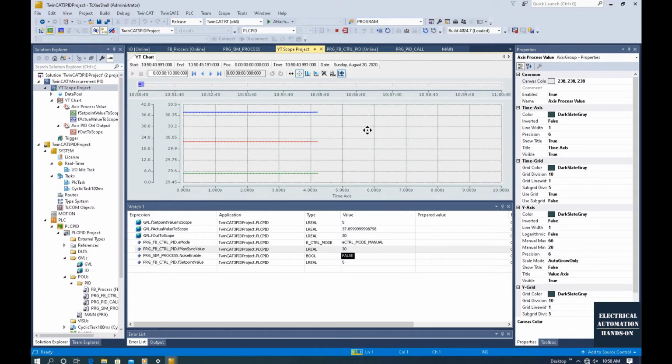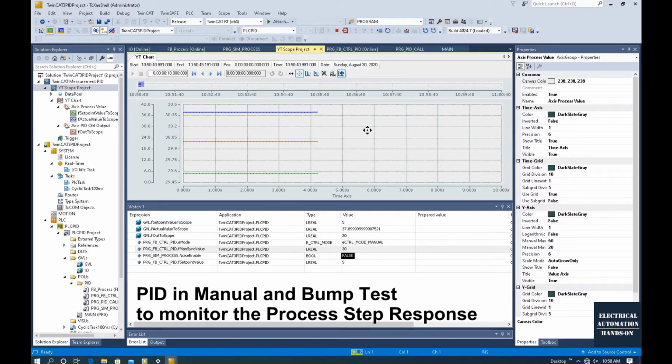So how can we select one value as the initial value of the gain? From my personal experience, we can give the system a step and get a stable response. Basically, we will then know the gain of our controlled object. Our PID gain will be 1 over the process gain, and maybe 2 or 3 times this 1 over gain. Okay, let me show how we can do that.